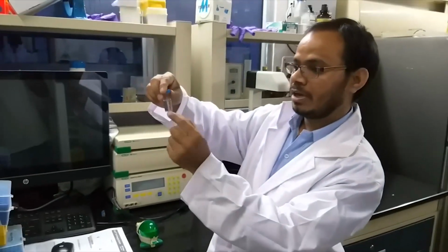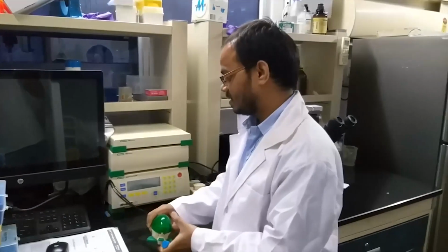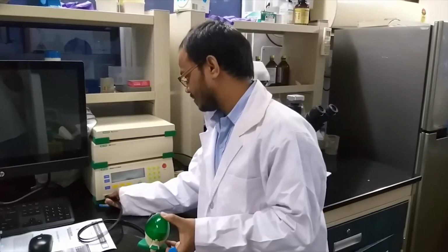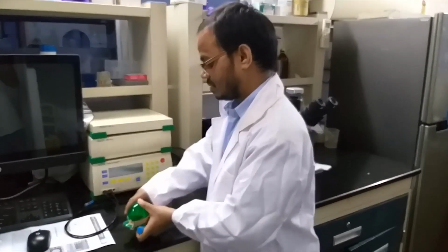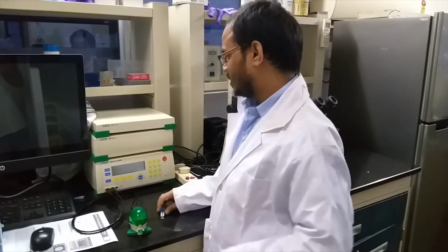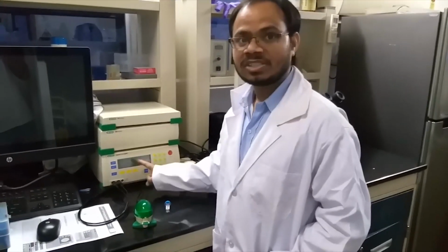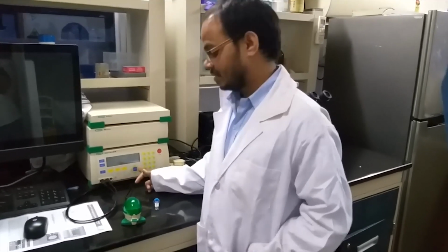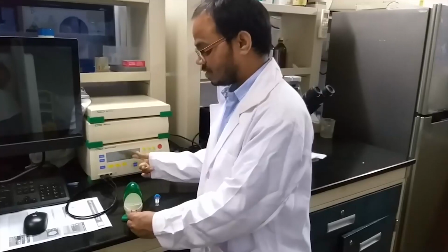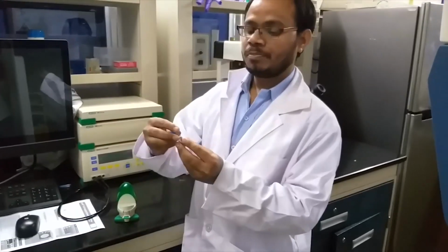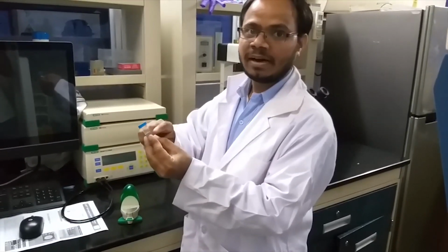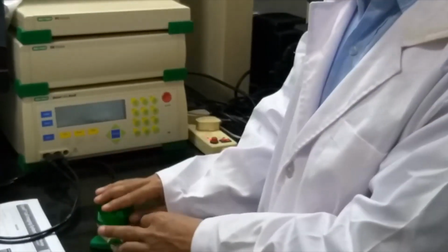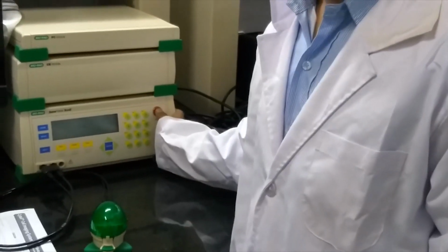There are two electrodes placed, and this is the sharp part. We will connect here like this, and all the adjustments, pulse, how much time we have to give the pulse, all these things we can set here. Once the setting is over, we can keep cells along with our plasmid DNA inside, and then hold, and we will press pulse.